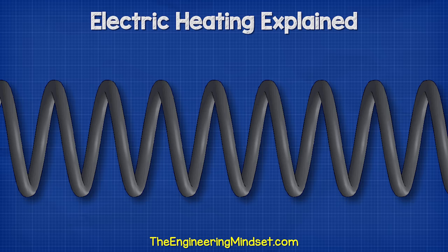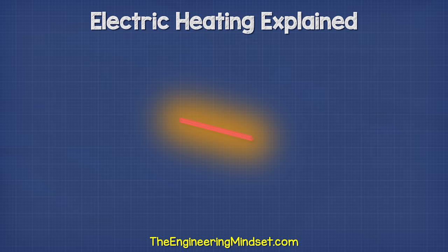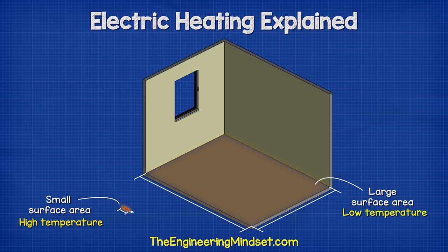With all of these methods, the heating element has a small surface area, so to transfer sufficient thermal energy, we need the heating element to reach very high temperatures. However, with underfloor electric heating, the surface area is very large as it covers most of the room. So the surface temperature is much lower, and the heat is distributed evenly across the entire room.